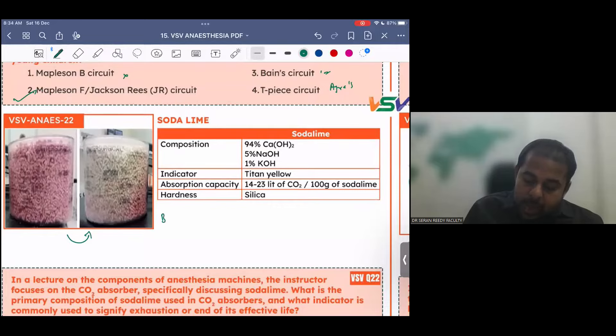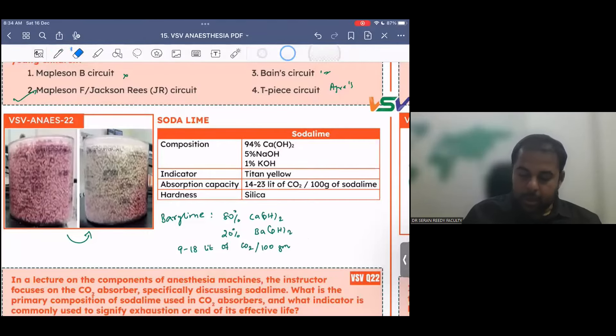There is another thing called barium lime. This barium lime, though the name is barium lime, again, still the major constituent, 80% is calcium hydroxide, and 20% is barium hydroxide, and it absorbs 9 to 18 liters of carbon dioxide per 100 grams of barium lime.